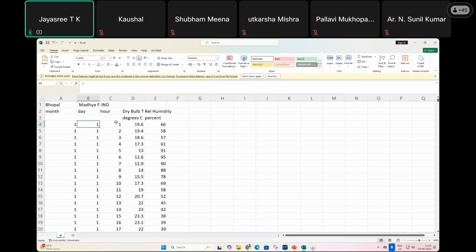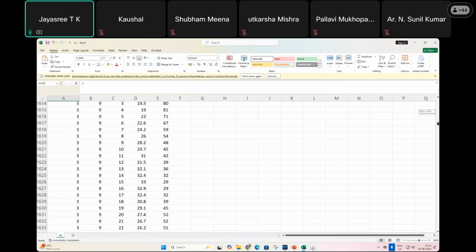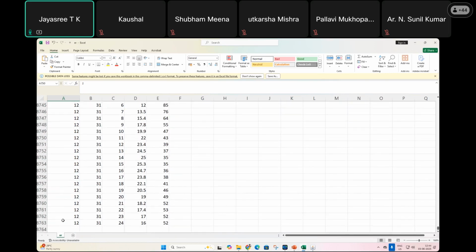On the first day, in the first hour, you have 19.6 degrees Celsius temperature and 66% humidity. Like this, you get it up to 24 hours. Then after the first month, you start the second month, February. Like this, you get it for 8,760 hours. For each day of the year, each hour, what is the temperature and humidity as per the weather.